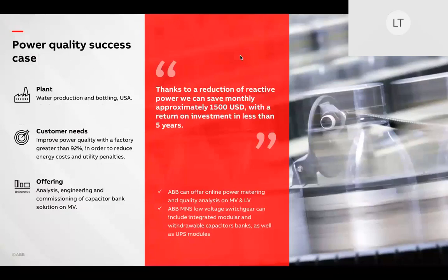Their request was to ABB to find out, firstly, what the status of their network was, and to propose a solution to improve the power factor to greater than 92% to avoid excessive utility penalties and, more importantly, reduce their energy cost. The local service team from ABB in their state provided a detailed analysis of the issue, which resulted in the installation and commissioning of an ABB medium voltage capacitor bank. This analysis and installation saved the customer around $1,500 a month, with a return on investment in less than 5 years. Doing the analysis up front and doing it correctly can lead not only to savings but greater efficiencies.